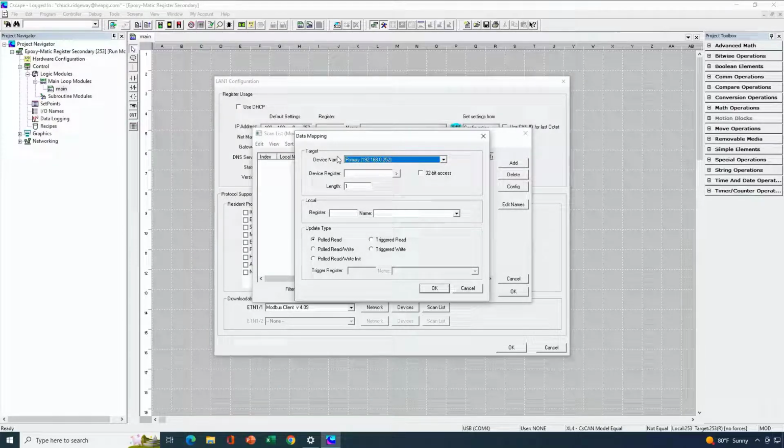So I will be reading and writing with that other OCS that's been selected for me. I'm going to go ahead and start reading at %R1, and I need to make sure I at least cover the first 18 registers, but I'm just going to go ahead and make that 32. So I'm going to read and write 32 registers.